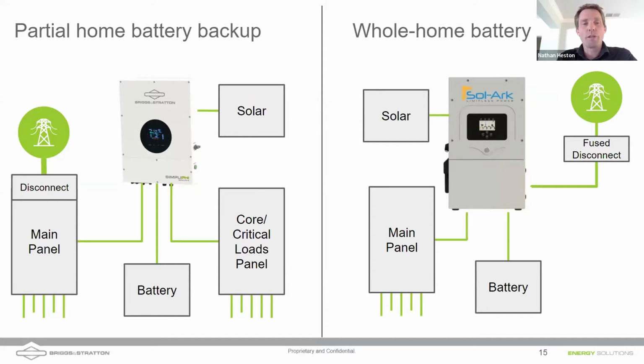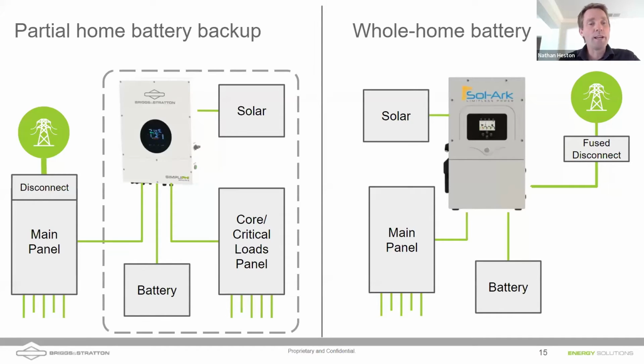If you have an inverter that's not capable of bringing 200 amps through it, like the Sol-Ark is, say the Briggs & Stratton inverter is only capable of bringing 40 amps through. You can't back up your entire load panel with that, because 40 amps is not enough power to power all of your loads, or even to just pass through that power. So you would have to install an extra loads panel. And that extra loads panel, in the event of a grid down situation, will isolate itself.